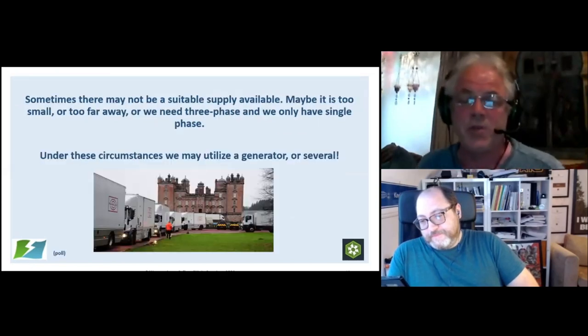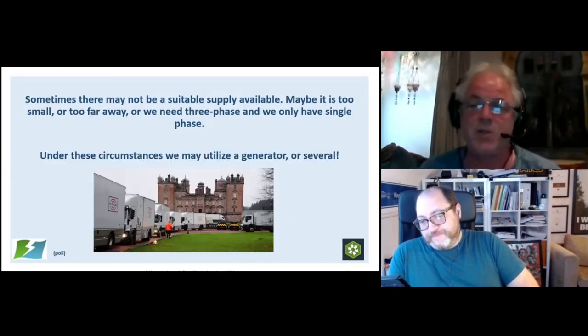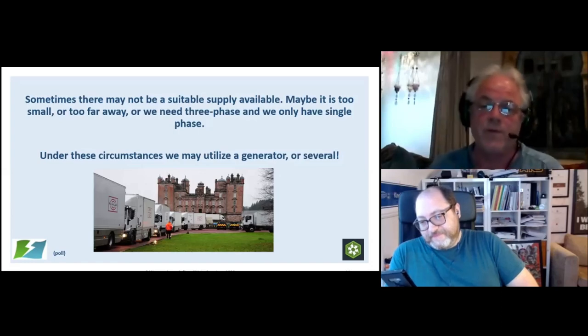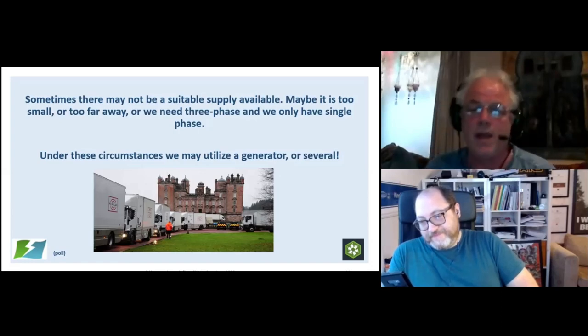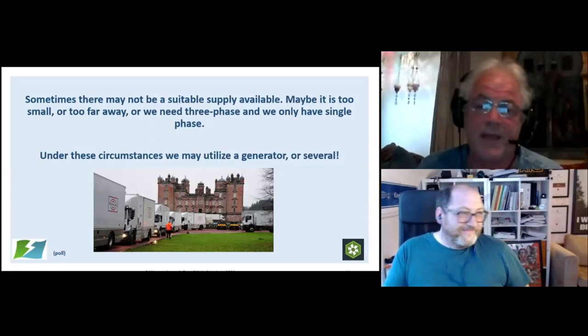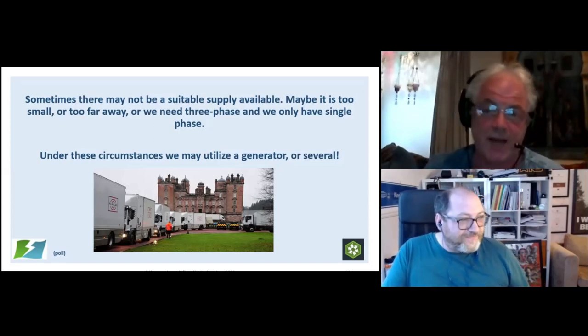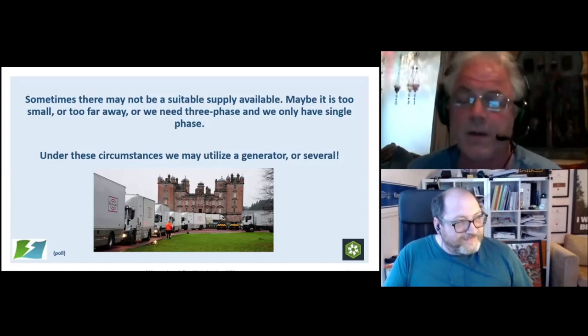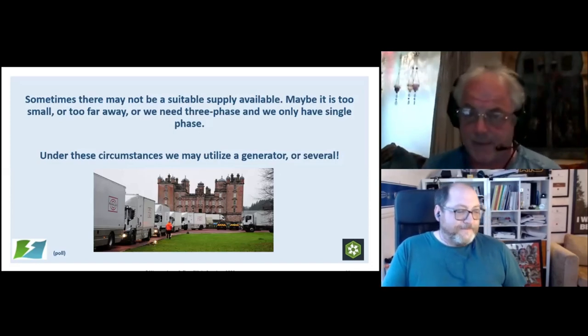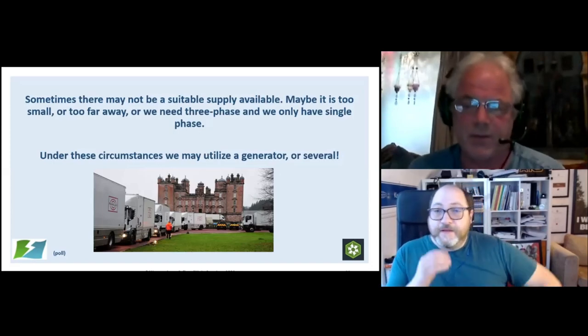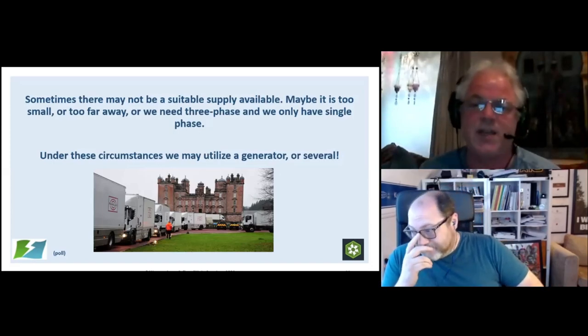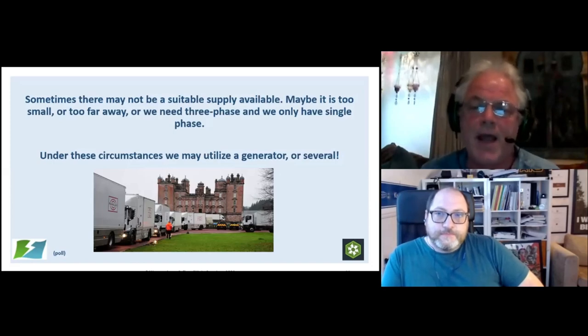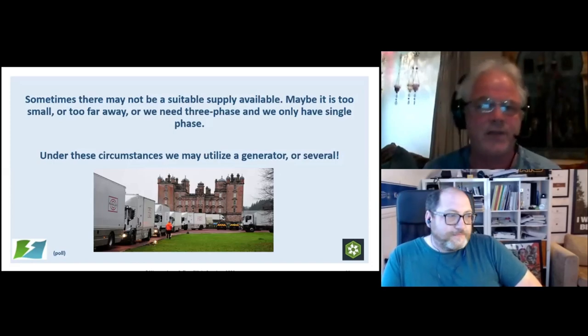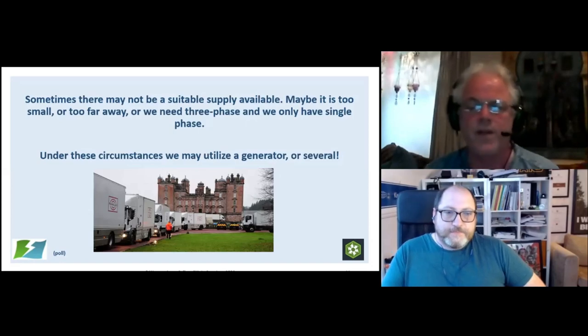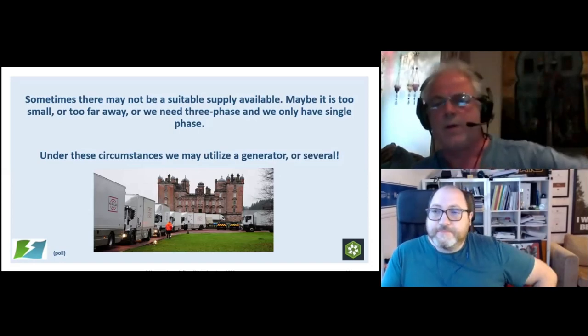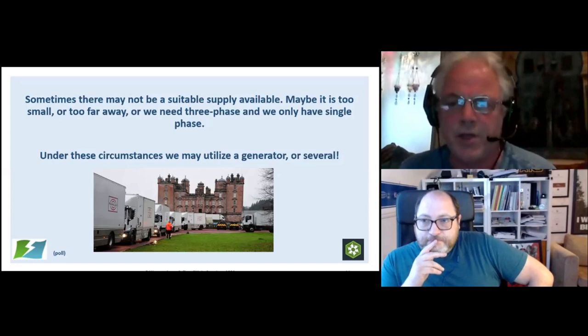Okay, so if we don't have a suitable supply, what can we do? If the supply is too far away, or we need three phase and we've only got a single phase as a fixed supply, under these circumstances we're going to need to use generators, or two, or 10, or 20, or 100, as many generators as we need. Now, generators are actually a wonderful thing because we can put generators much closer to our centres of load. And that means we can cut down on the length of distribution cables and so forth. And if we need a bit more supply, then we can actually put more generators in.